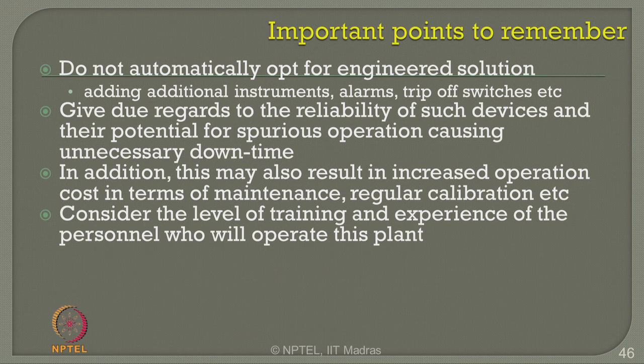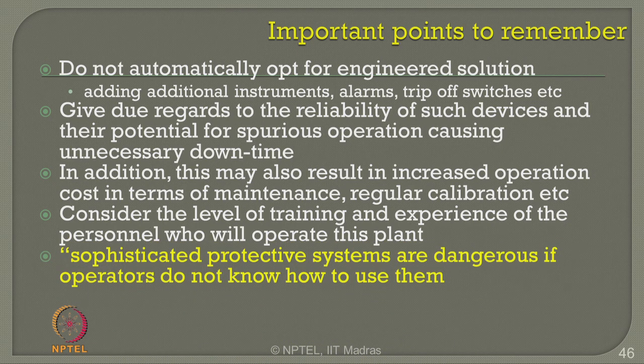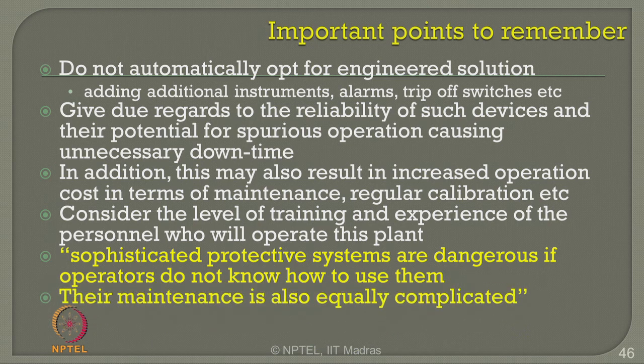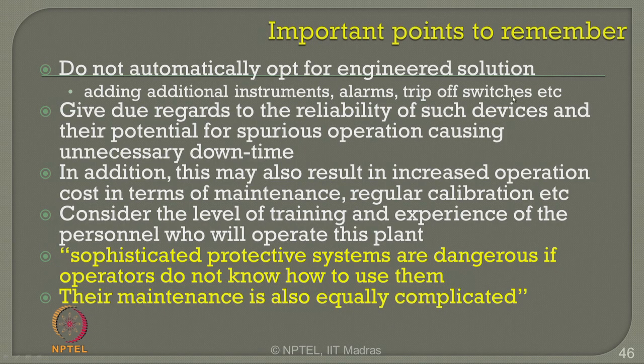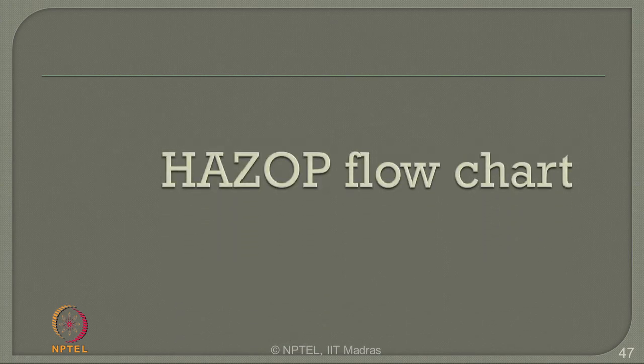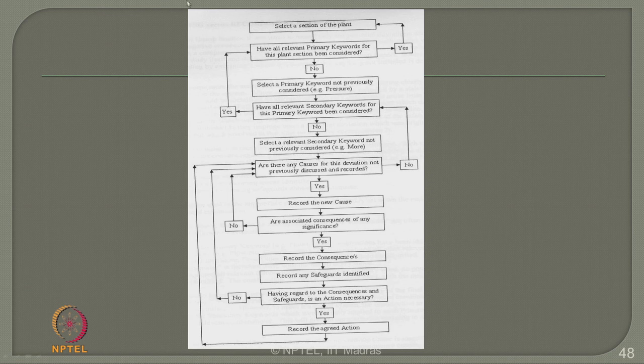Consider also the level of training imparted to the people who are expected to operate these kinds of alarms and instruments. Please understand, sophisticated protective devices are dangerous if operators are not trained how to use them. Therefore, maintenance also becomes equally complicated. So, advocating additional instruments, alarms, and trip switches should not be the only solution in the recommended action of a HAZOP report. Let us quickly see how a HAZOP flowchart looks. Select a section of the plant, have all relevant primary keywords in place.